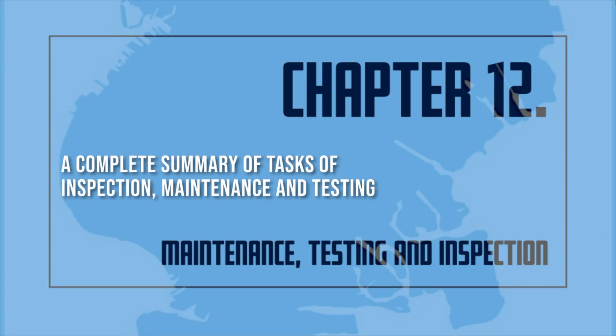Spare sprinkler heads/wrenches. The supply shall be inspected annually for the proper number and type of sprinklers and a sprinkler wrench for each type of sprinkler. Sprinklers. Sprinklers shall be inspected from the floor level annually for signs of leakage, corrosion, foreign materials, paint, and physical damage, and shall be installed in the proper orientation, such as upright, pendant, or sidewall. If the above problem occurs, the sprinkler shall be replaced. Glass bulb sprinklers shall be replaced if the bulbs have emptied. Unacceptable obstructions to spray patterns shall be corrected.